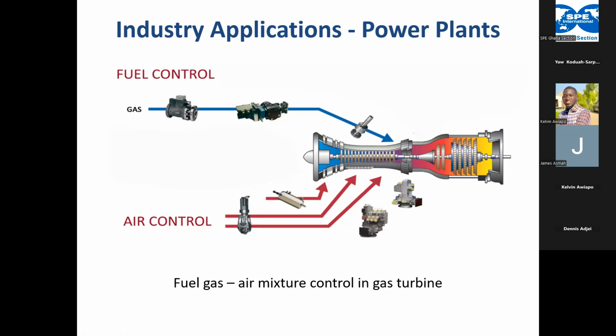You have to drop it also to keep the speed of the turbine constant. So in that case, you have the governor, which will always be calculating based on the load that is being served at a time. If the load increases, it will recalculate and bring in more gas flow into the system, and the air as well. So that's this fuel gas air mixture control using the same process control approach to ensure that you have the turbine running all the time.